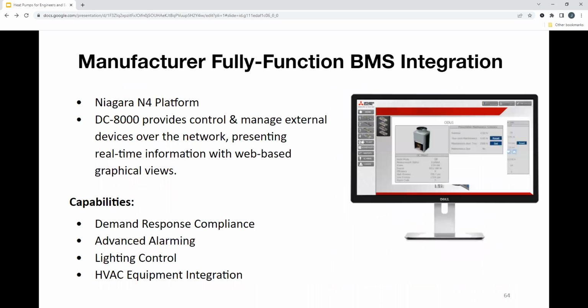And from a manufacturing standpoint, the largest set of controls you can add on a project is their BMS system, which is a Niagara N4 platform utilizing a DC8000 controller. Provides control, managed external devices over the network, presenting real-time information with web-based graphical views. So some of the capabilities that it can do is demand response compliance. We got your advanced alarming, lighting controls, HVAC equipment integration. Can pretty much do it all besides life and safety. We don't tie into that.